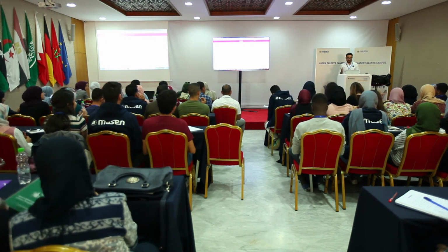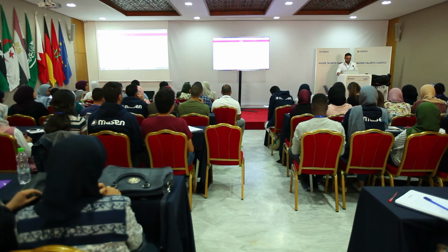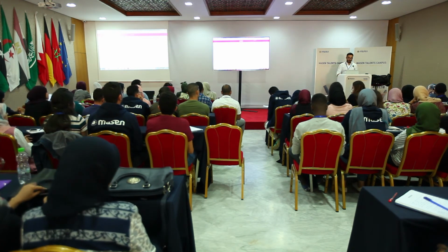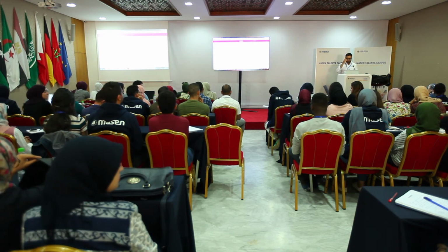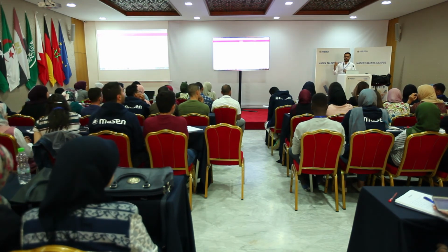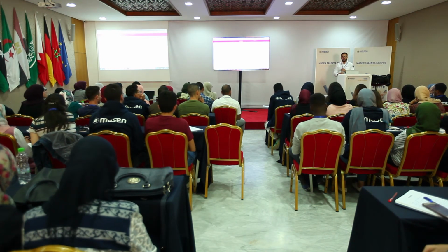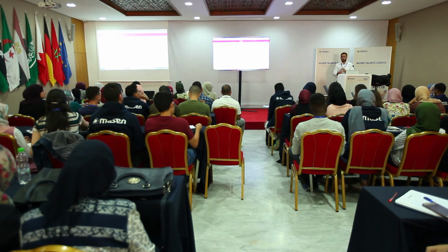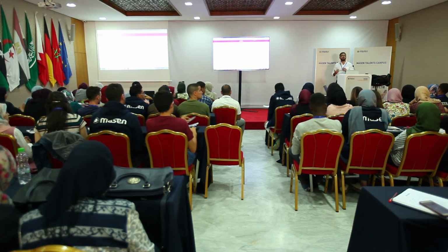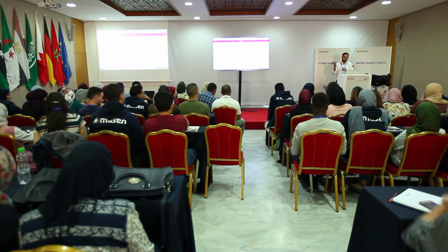Of course, if you let the salts reach their freezing point, which is 280, then we have an emergency because they will convert into solid. They will freeze. And then it takes a lot of energy and time to actually melt them again. But that never happens because, of course, you won't let that happen. And the whole system is fully traced, so you have electricity in case you need it to guarantee that they're always above the freezing point.